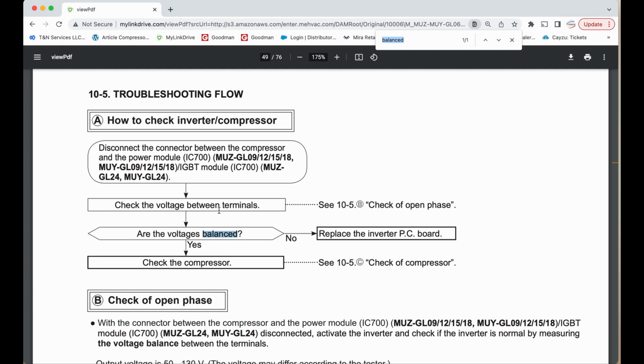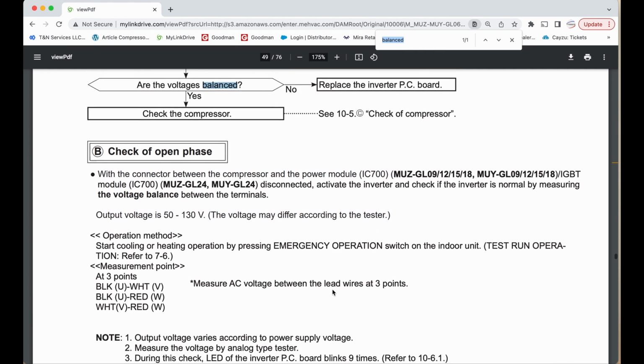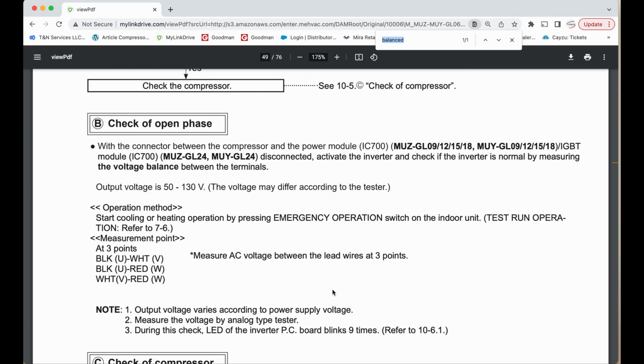Check the voltages between the terminals. Are the voltages balanced? If they aren't, then you replace the inverter board. If they are, then you check the compressor. It says see 10-5C, check of compressor, right? So we're just going to scroll down here. What we're really looking for is this B section right here, check of open phase.